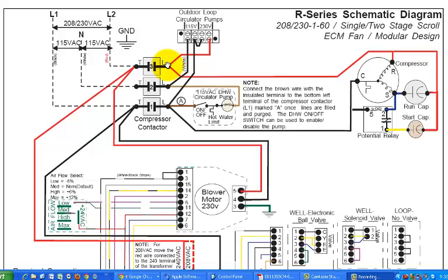And we're going to have 115 volts available to us between the middle terminal and either one of the upper or the lower terminals. So we've got that ability to draw 240 or 230, whatever it happens to be in your particular area or particular time of day, off on that right-hand side when there's a call for compressor action. And so if we follow that through, recognizing that if we were to put our voltmeter between there and there, we've got 240 volts. If we follow this line, the red line on the diagram, across and over to the compressor structure, we'll see that it is indeed feeding the compressor. Similarly, if we follow the other line, it's going to come over, and again, when the compressor contactor is actuated, it's going to show the compressor power on this side.